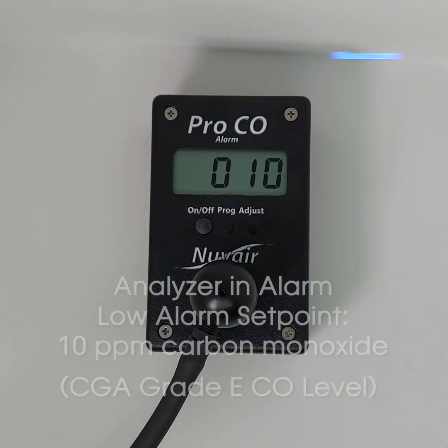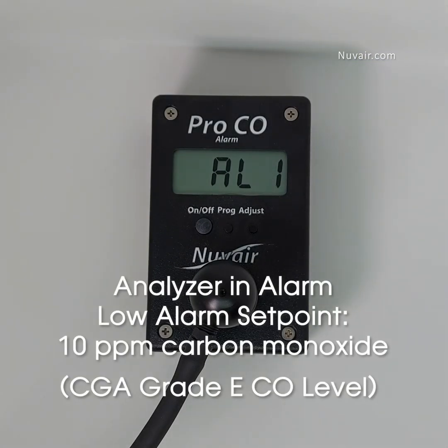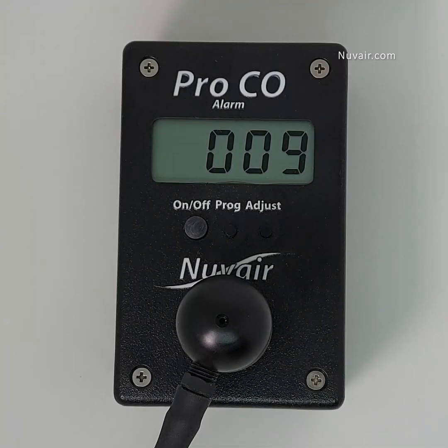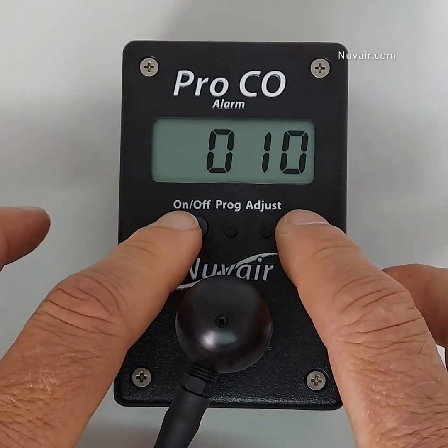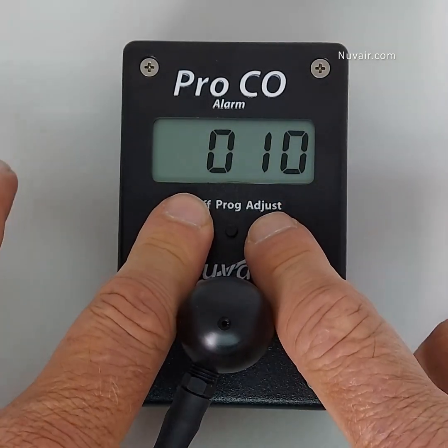This video is the quick start guide for the Nuvair Pro CO Alarm Handheld Analyzer. The Nuvair Pro CO Alarm detects carbon monoxide, or CO, in stored gas cylinders, enclosed spaces, and compressors. With a range of 0 to 50 parts per million, the Pro CO is equipped with two user-programmable alarms that sound if carbon monoxide levels exceed one or both alarm setpoints. High and low setpoints are programmable by the user, and one or both alarms can be disabled.